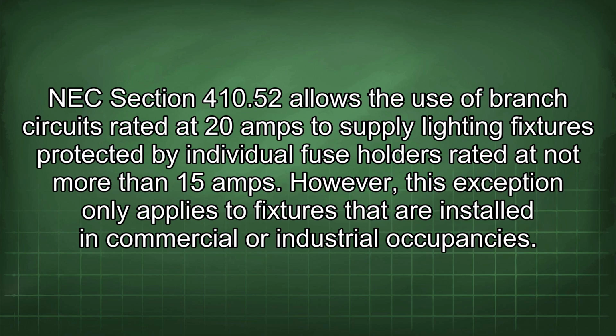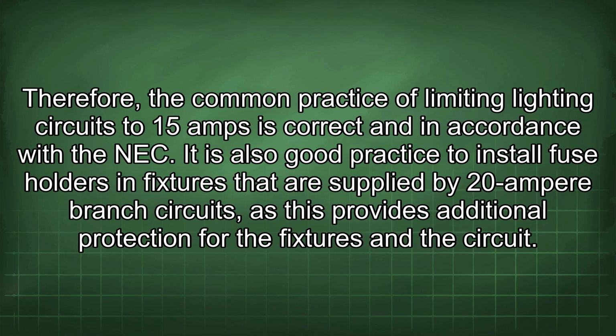However, this exception only applies to fixtures that are installed in commercial or industrial occupancies. Therefore, the common practice of limiting lighting circuits to 15 amps is correct and in accordance with the NEC. It is also good practice to install fuse holders in fixtures that are supplied by 20 ampere branch circuits, as this provides additional protection for the fixtures and the circuit.